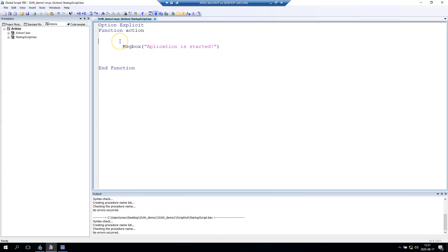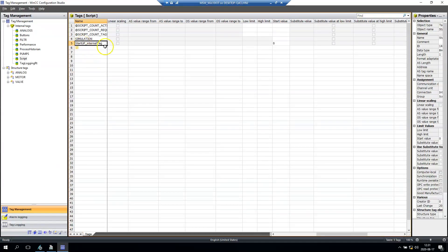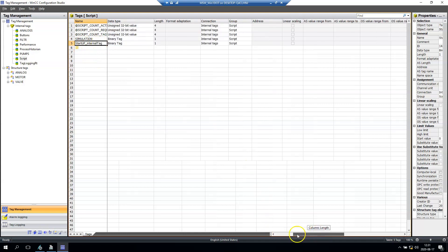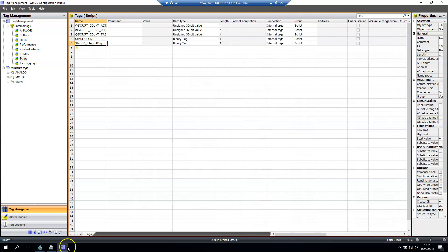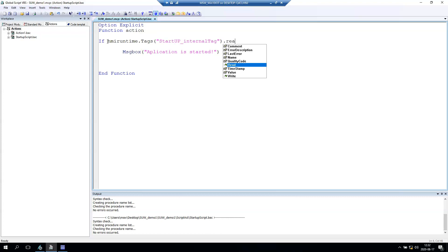But now let's go and change the action script to make this only once when our starter tag is zero. Let's go to script and write an if-then function. So if HMI runtime tags read is zero, we want to display this message box and we need to close.